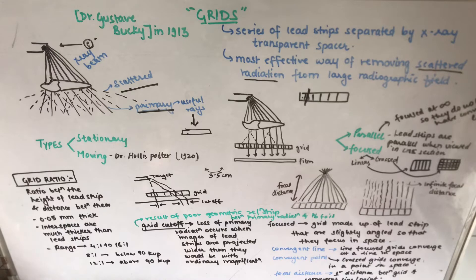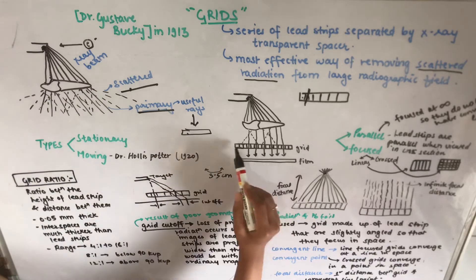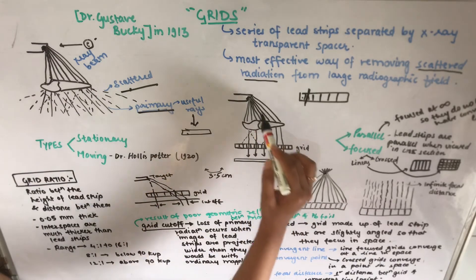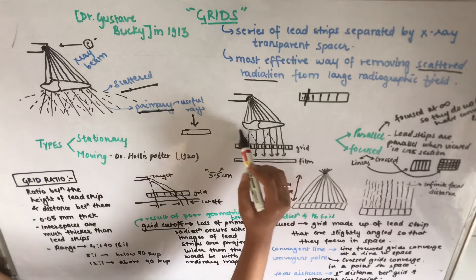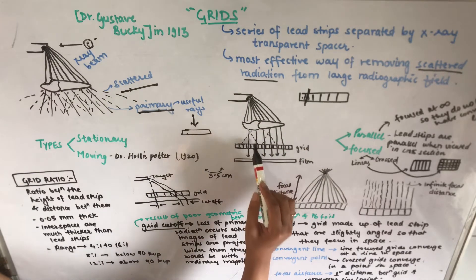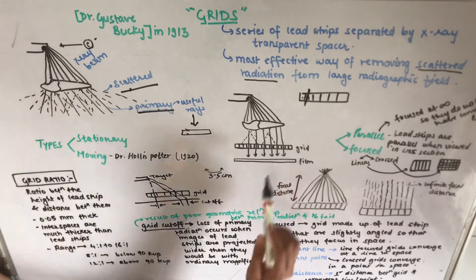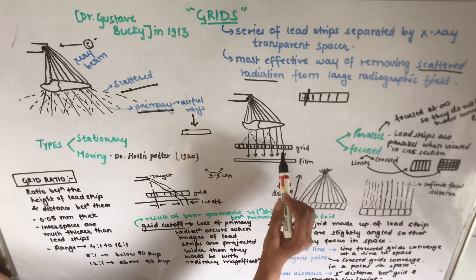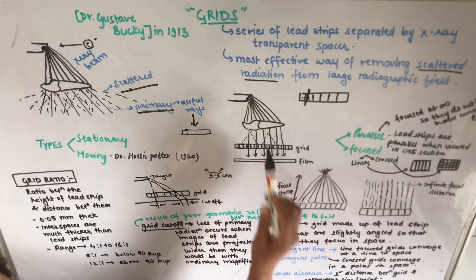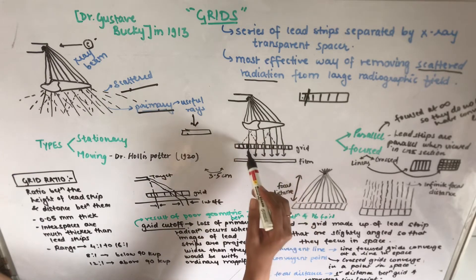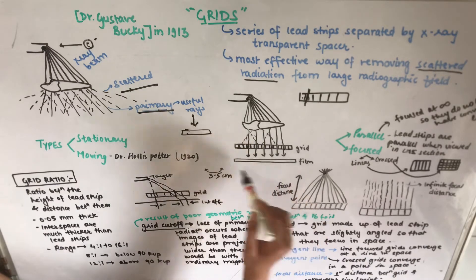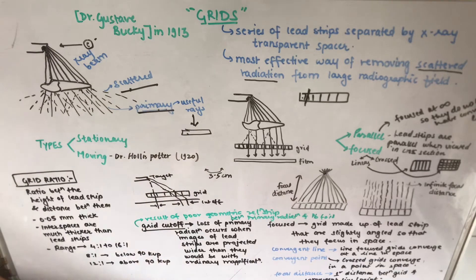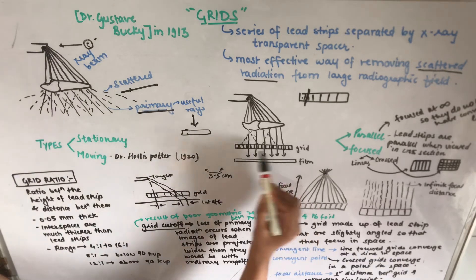This grid was given by Dr. Gustave Bucky in 1913. It is placed between the object and the film. When the x-ray beam hits the object, scattered and primary radiations are produced. The lead strips in the grid absorb the scattered radiation, so only the primary radiation reaches the film, improving image quality.